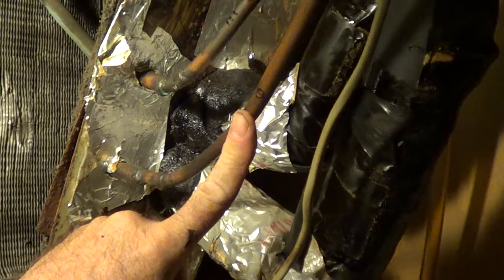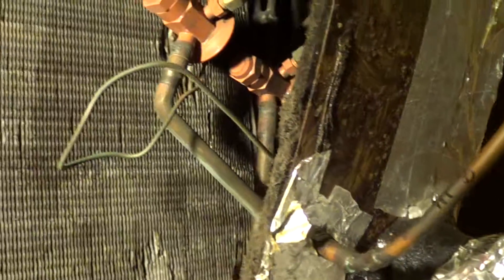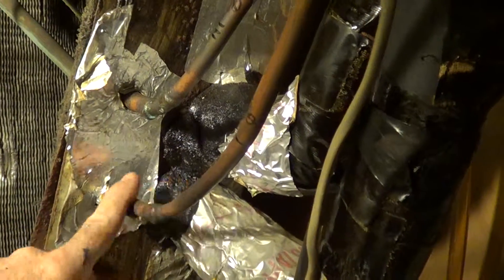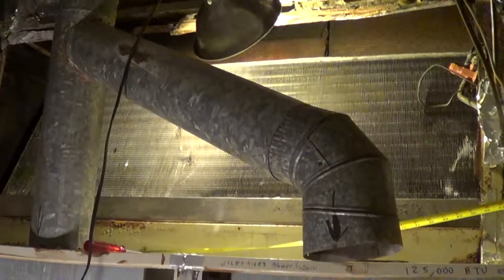This install always vibrated when the single-phase line ran. It seems like they didn't put enough vibration-dampening material on there to prevent it from vibrating. Because of that vibration it probably went ahead and busted a braze fitting. I'd be really happy if it broke something right here where you can just get at it, but this hasn't been looked at for about 12 years — we've been running on one air conditioner. This is the drain line, and there's an integral drain pan here with the evaporator coil.